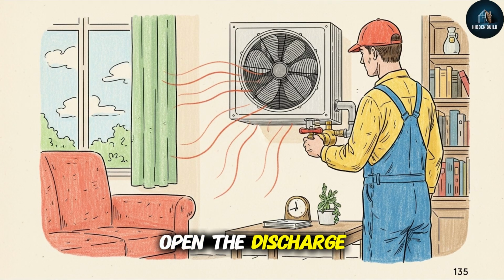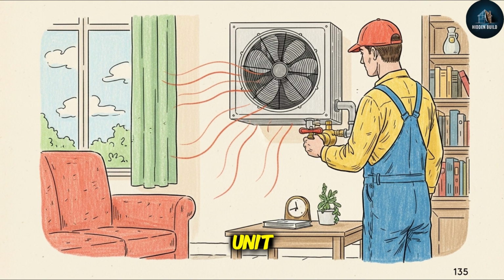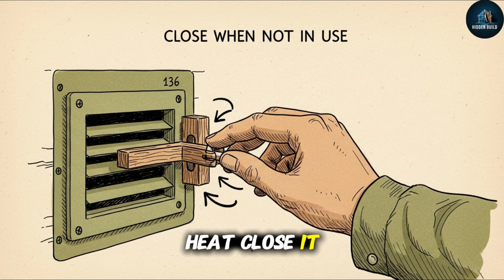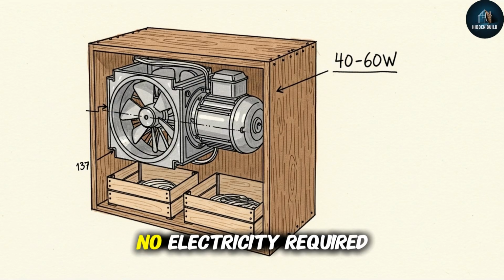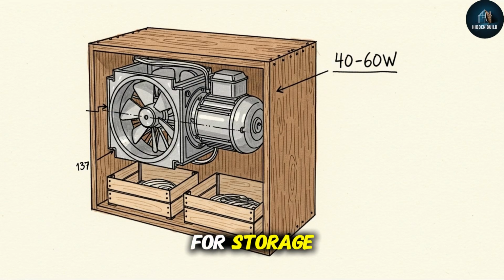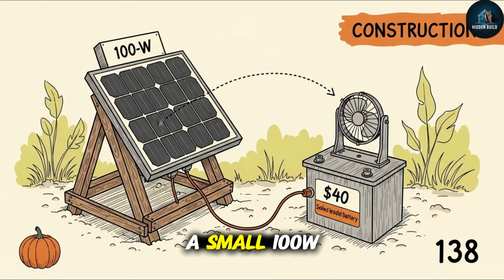The sand holds that heat through the night, through the next day if the insulation is good, through a 2-day storm if the drum is properly sealed. Open the discharge valve connected to the fan coil unit when you need heat. Close it when you do not. That is the entire operating protocol. No electricity required for storage. The fan coil unit draws 40 to 60 W when running. A small 100 W solar panel with a $40 sealed lead-acid battery handles the fan completely off-grid.